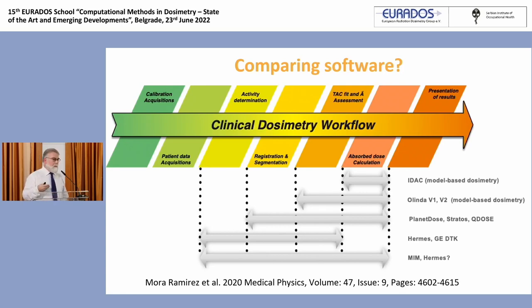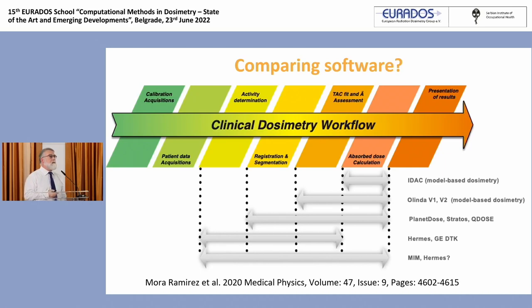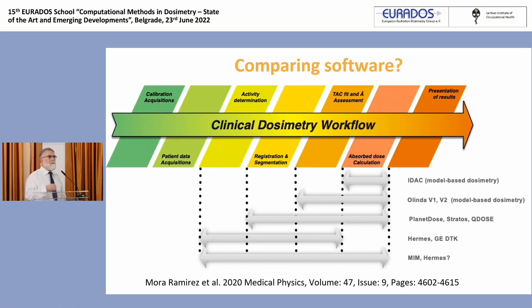For example, Hermes or MIM can do reconstruction — from activity determination to sometimes absorbed dose calculations. But some, like IDAC, require you to provide all the pharmacokinetic parameters; it doesn't do reconstruction, segmentation, or registration. It has to be said that most of the commercial codes currently available do not do reconstruction, but use reconstructed images with a calibration factor and do all the other steps up to the absorbed dose calculations.